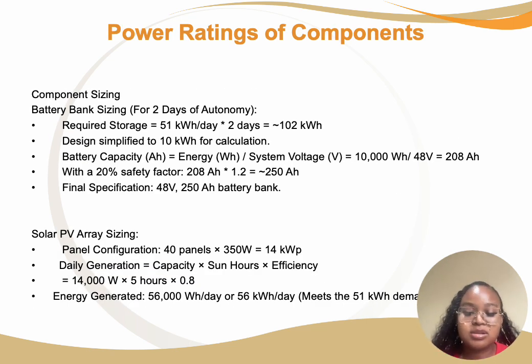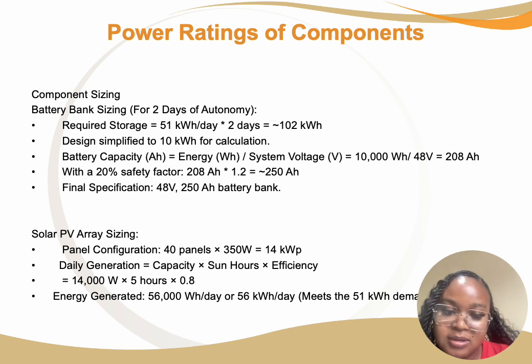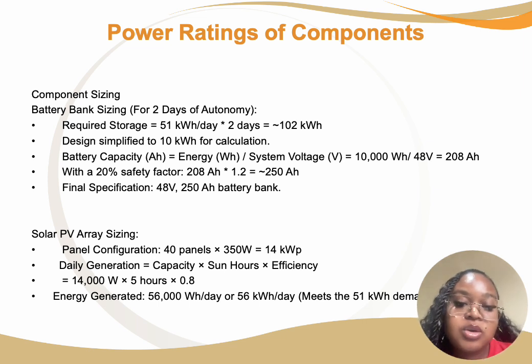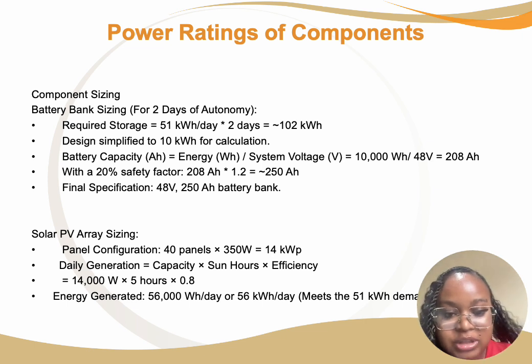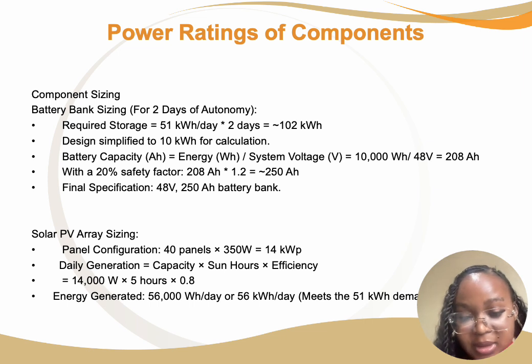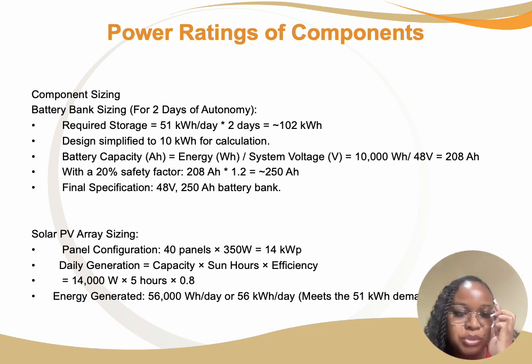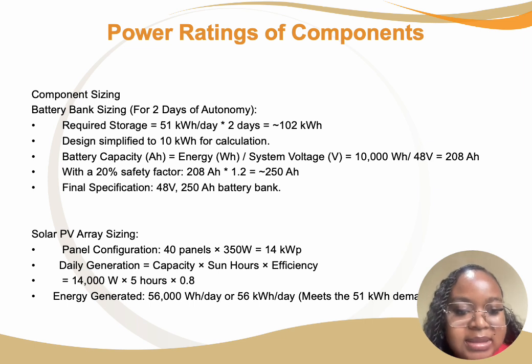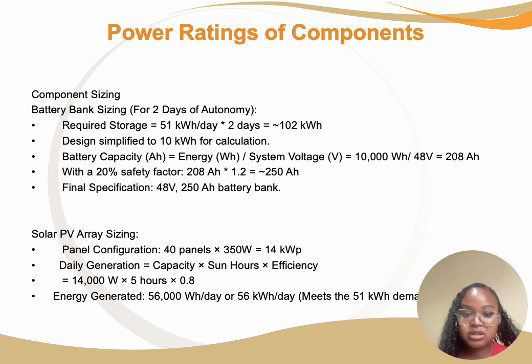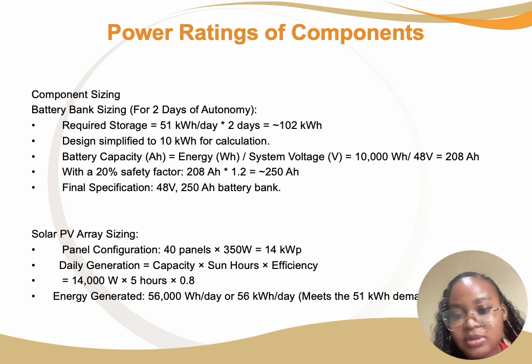Then we calculated power ratings of our components. For the component sizing, we started with the battery bank sizing. The required storage from our previous calculations was 51 kilowatt hours per day. We were using 2 days of autonomy, so 51 kilowatt hours per day multiplied by 2 days is 102 kilowatt hours. Then the design was simplified to 10 kilowatts for calculations. The battery capacity in amp hours is energy divided by system voltage. The system voltage we were given is 48 volts.